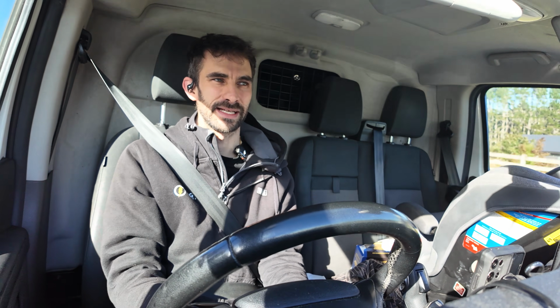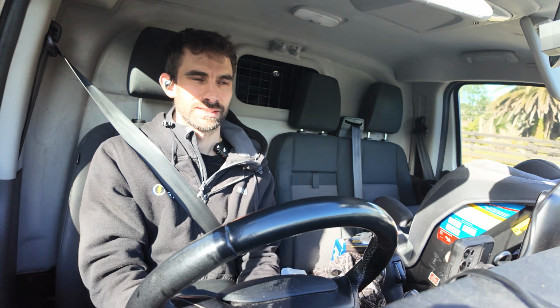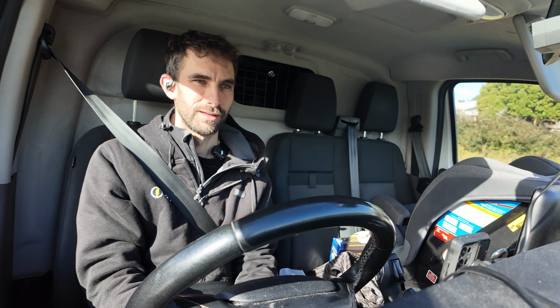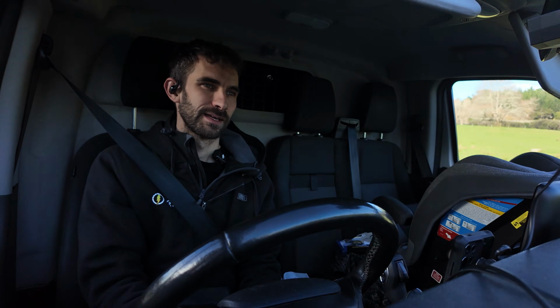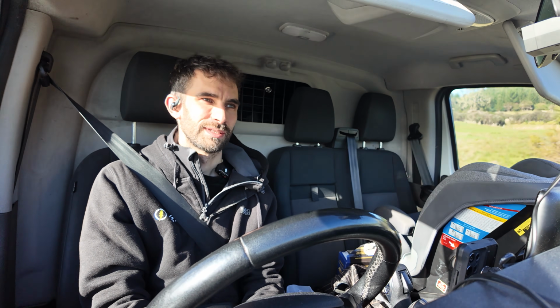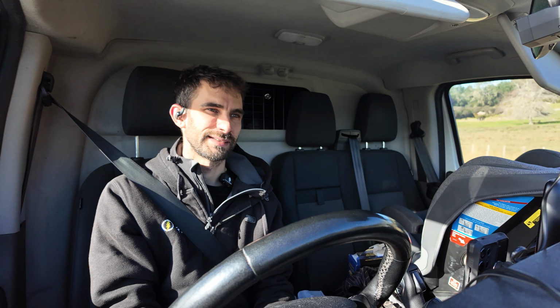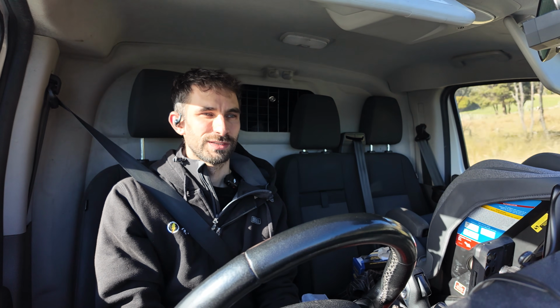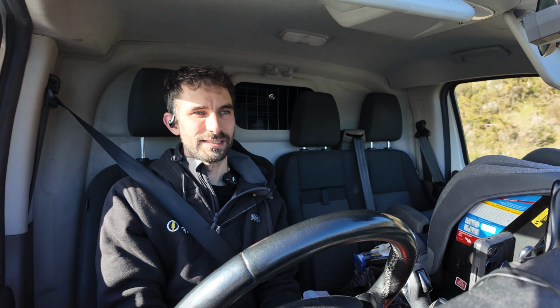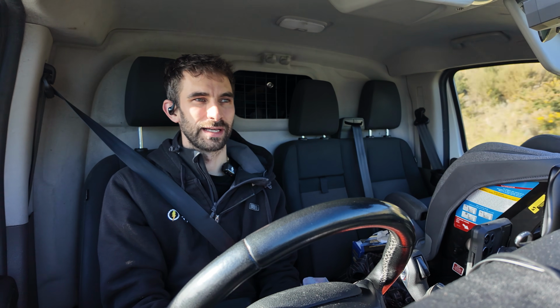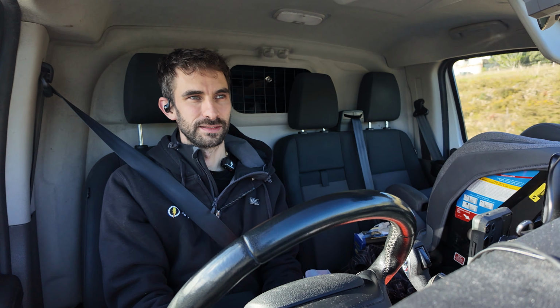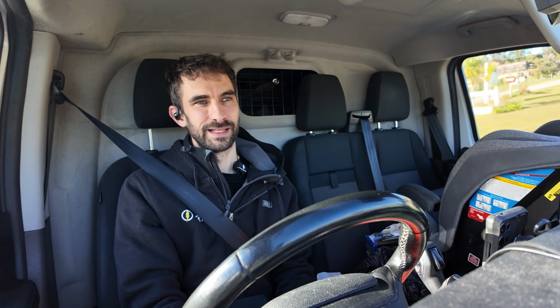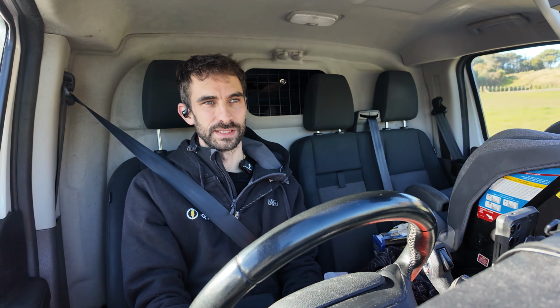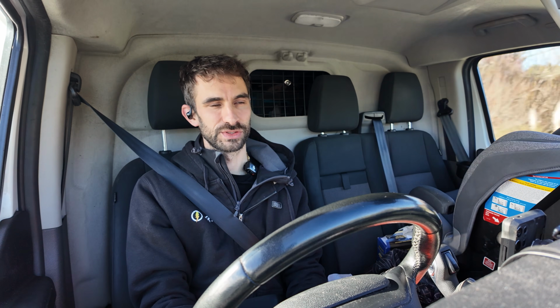So New Zealand has what's called an MEN system. Overseas, I think it's called a TN-C-S system. I should probably have those letters right if I'm going to record a video. If it's wrong, I'll edit something in. Terra, neutral, connected, separate. So they are connected coming into the house, and then they separate in the distribution board and the main switchboard. We have an MEN link, and then around on all the final sub-circuits, there's separate earthing conductors and neutral wires.